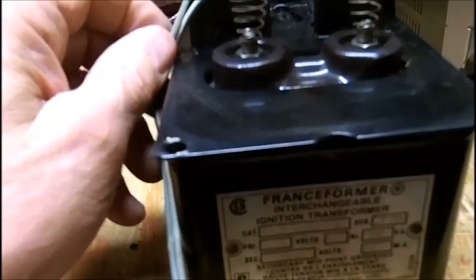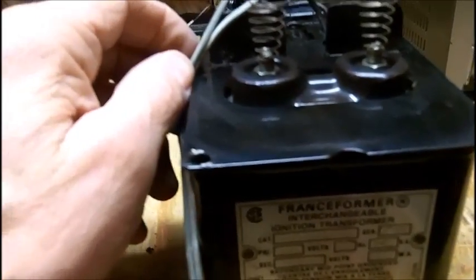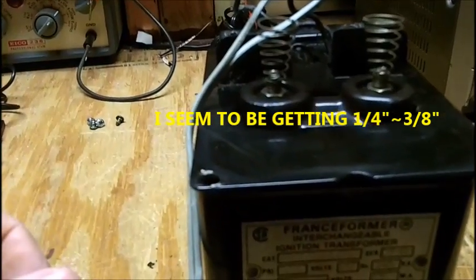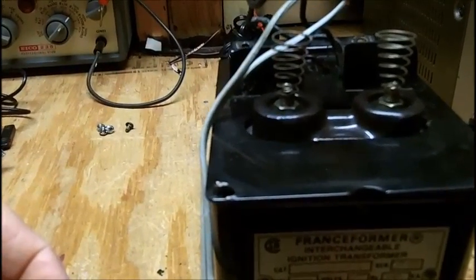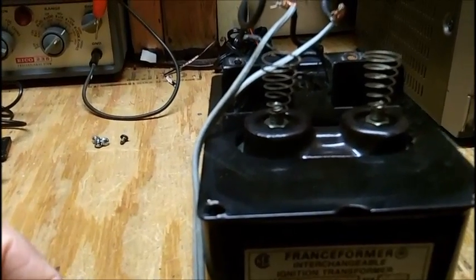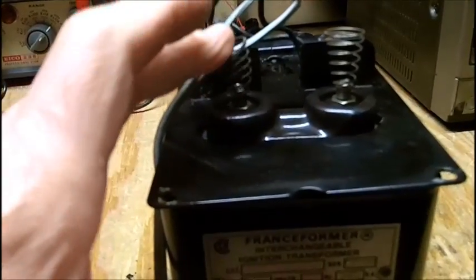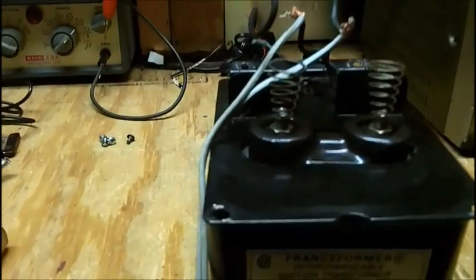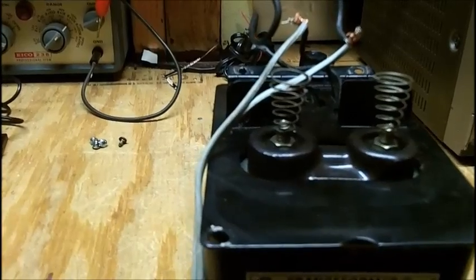Well, I thought I was getting 3/4 of an inch of spark, but I'm getting a lot less than that. I'm estimating it might be about 1/4 inch, but on AC you're supposed to get a longer arc for the same amount of voltage compared to DC voltage, and we're not getting it. Usually the spark would go almost 3/4 of the way over to the next terminal, and that wasn't the case. I was only getting a drawn arc about 1/4 to 3/8 of an inch, as I showed on this video.